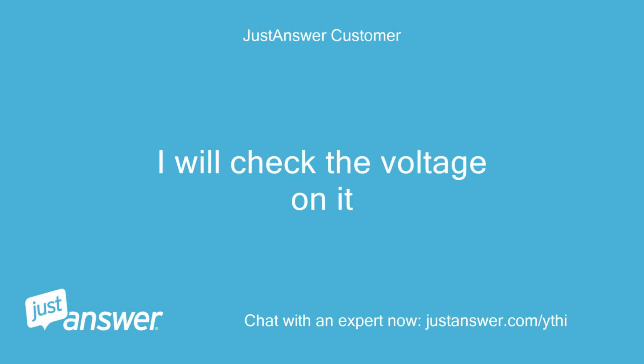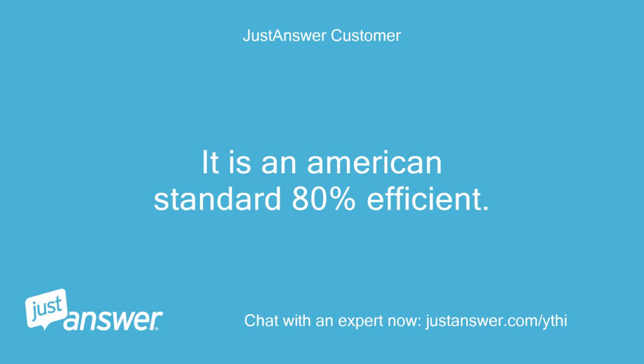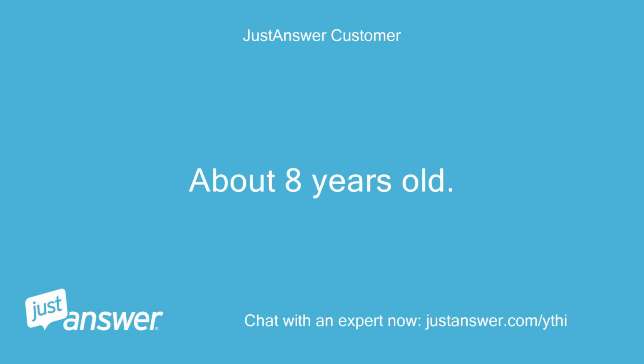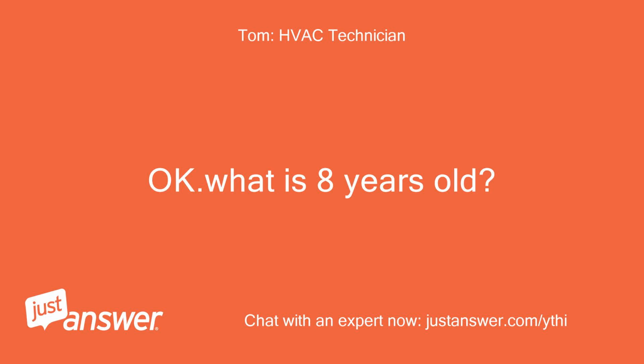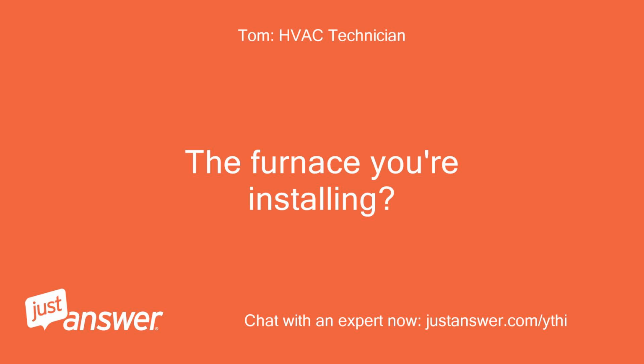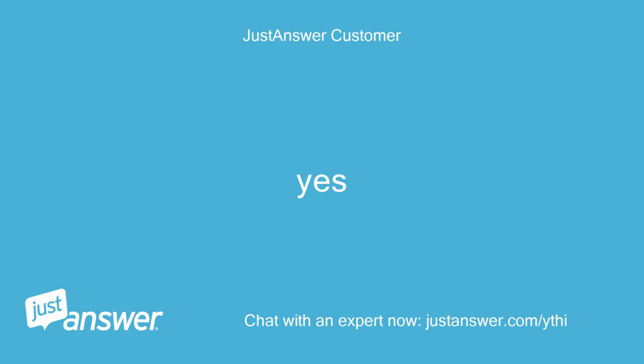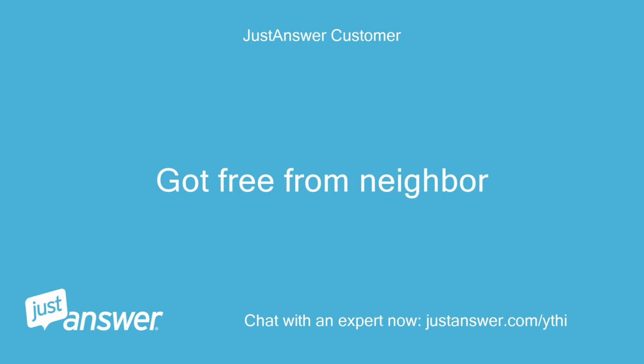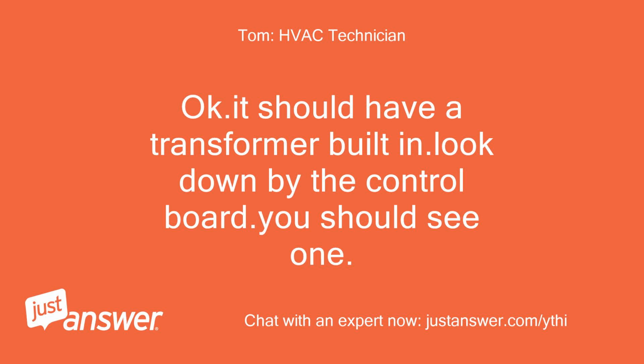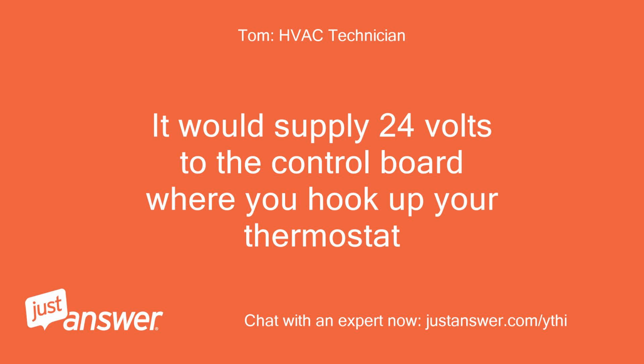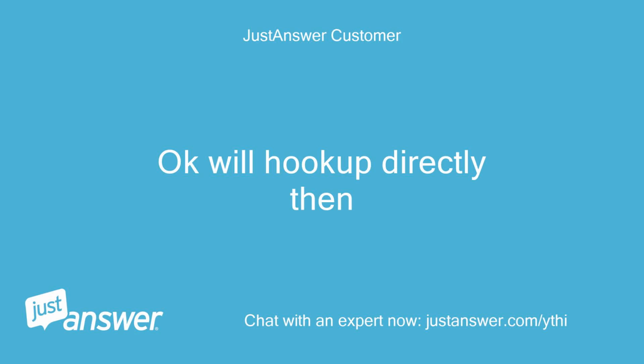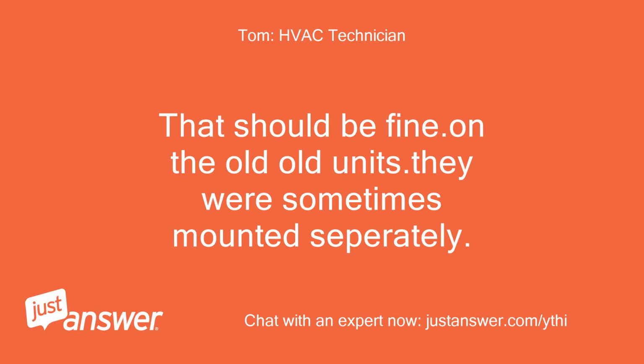I will check the voltage on it. It is an American Standard 80% efficient. About 8 years old. Okay. What is 8 years old? The furnace you're installing? Yes. Got free from neighbor. Okay. It should have a transformer built in. Look down by the control board. You should see one. It would supply 24 volts to the control board where you hook up your thermostat. Okay, we'll hook up directly then. That should be fine. On the old units, they were sometimes mounted separately.